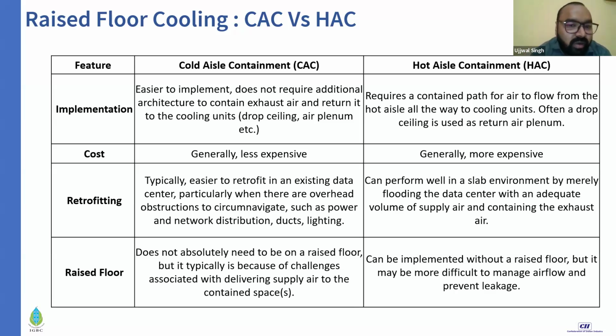So your whole data center is filled up with that air. Even if your cooling system goes down, or something happens to it for a fraction of a second or even a minute or so, you have a good amount of thermal mass of cold air enveloping all your server areas. So it gives you a very good cushion, and you feel much more secure in the event of a cooling failure when you have hot aisle containment.